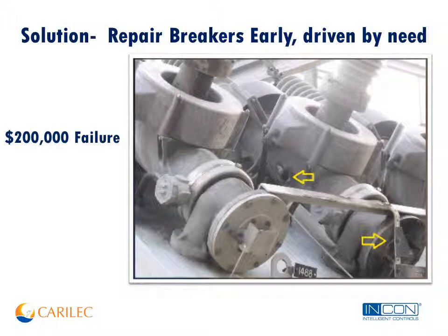And the desiccant bags were also completely saturated in these breakers. So this was a failure that occurred just randomly. This picture doesn't show it, but it was quite a violent explosion. It took out some sheds on some standoffs and some of the surrounding equipment. It made the news, and it was the kind of publicity the utility really didn't want.